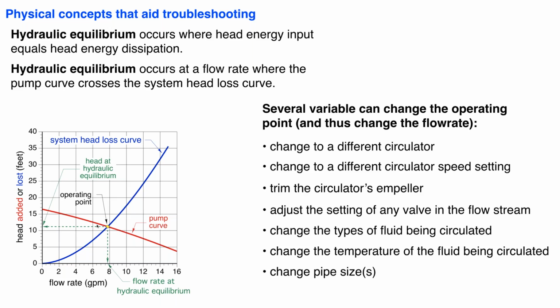Certainly if we change pipe sizes, okay? So these are all things that could affect that flow rate. And adding or removing components from a flow path. If we add another valve to a system, if we add another heat emitter in a circuit, that is going to affect that system curve, and it's ultimately going to affect where that operating point is. So again, from a troubleshooting standpoint, understanding how the circulator interacts with a piping circuit is important.